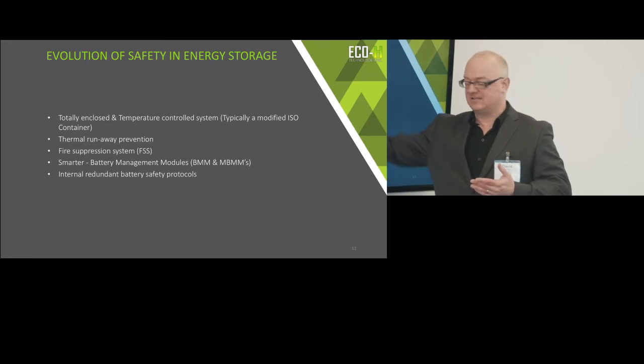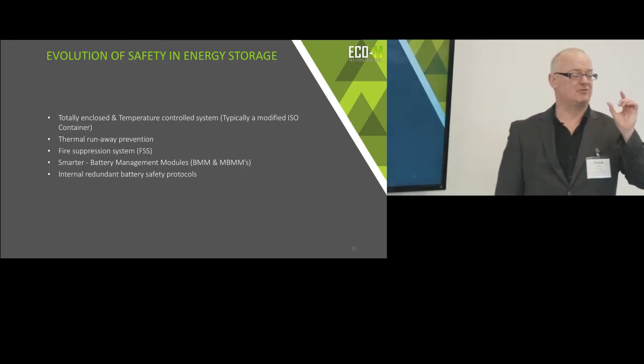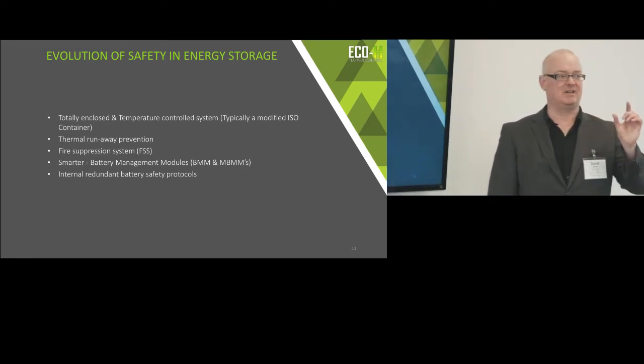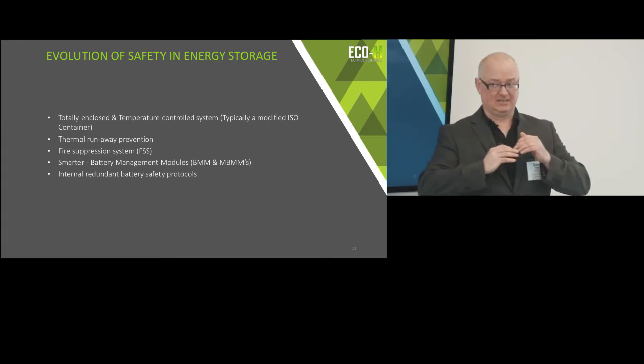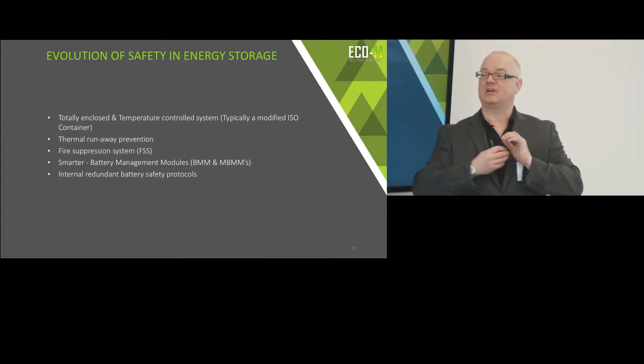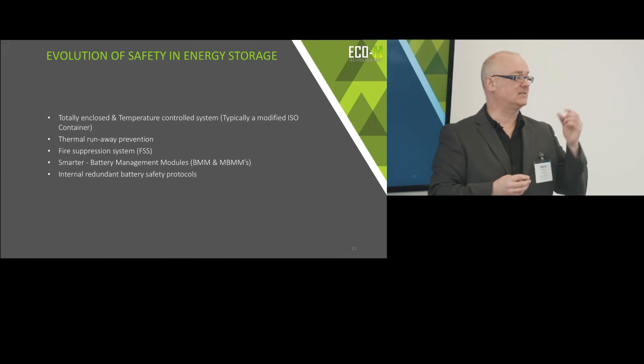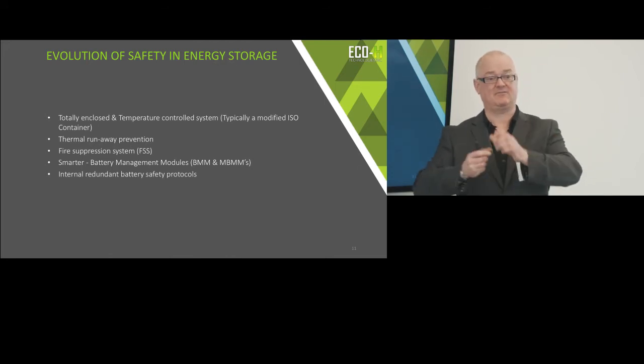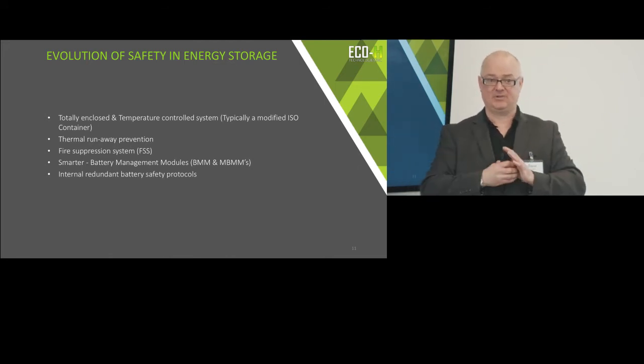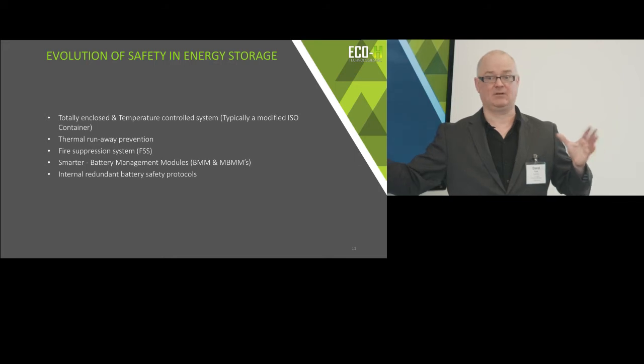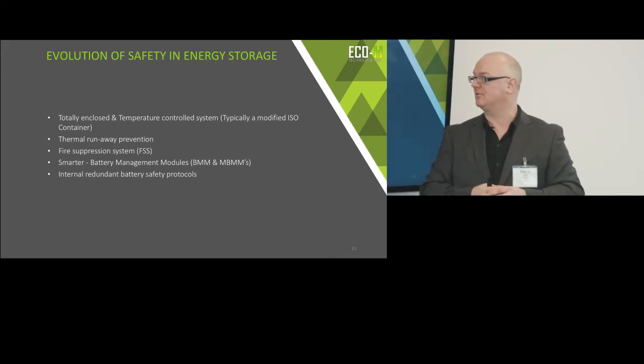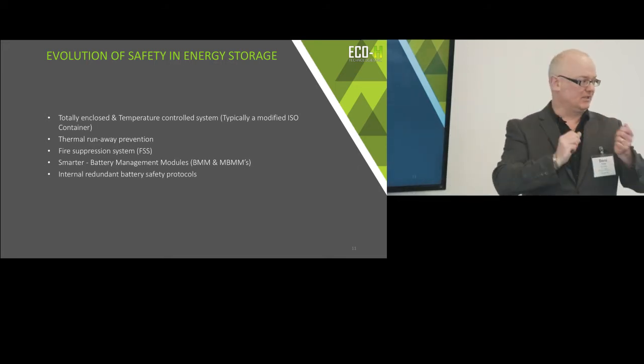Inside these are microcomputers or microcontrollers measuring overvoltage, undervoltage, overcurrent on discharge, and overcurrent on recharge. They check the cell temperature in every battery, in every string, in every system — which could be thousands of cells in one unit — and they're monitoring all of this all the time.